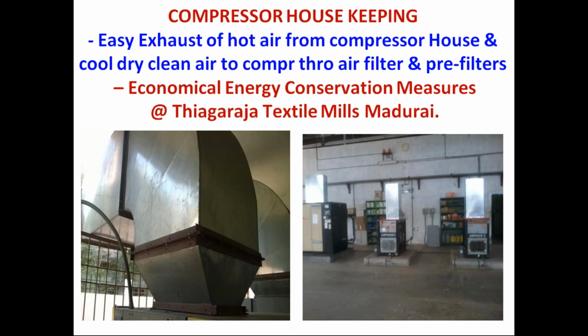Compressor housekeeping. Again, I am just touching on the symptoms of energy loss that are happening in the industry. This is a point towards energy conservation. Once you go into the industry, the ambient temperature is around 35 to 40, let us say. And once you enter the compressor house, if you find the temperature very much more, and you cannot stand in the compressor house for more than 10 minutes, it shows the RH is very dry and the temperature is 5 or 7 degrees or much more. This itself is an energy loss at the generation itself. The compressor is drawing a higher temperature and automatically the generation loss goes up. In some places, the generation loss goes up to more than 10%, because the filters get choked and the hot air getting out of the exhaust comes back to the suction.